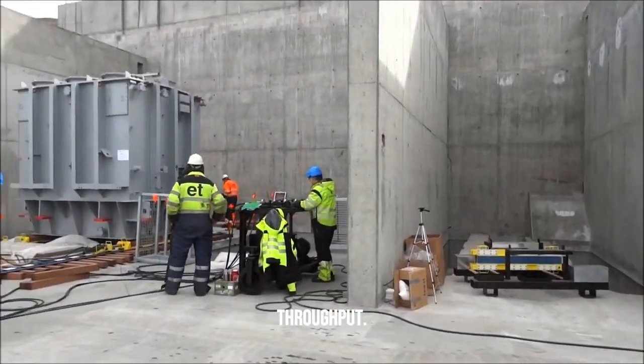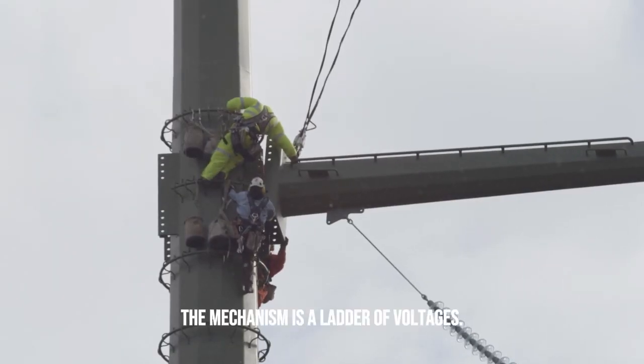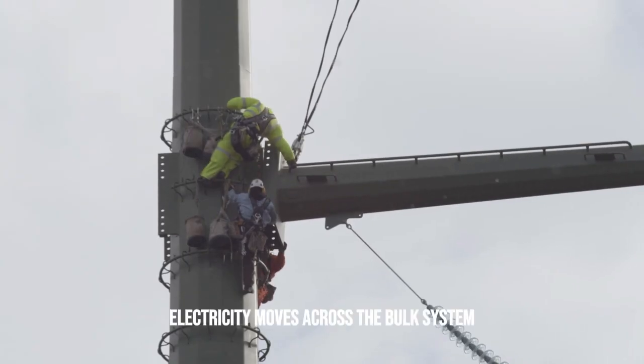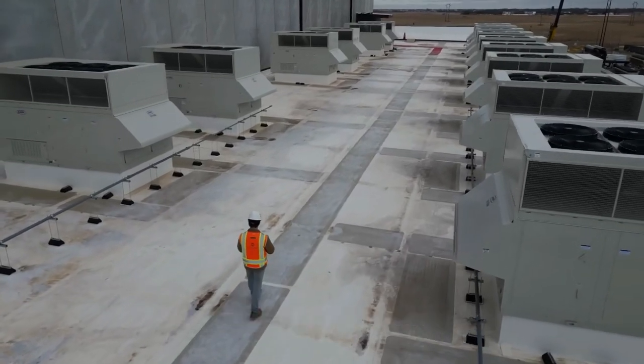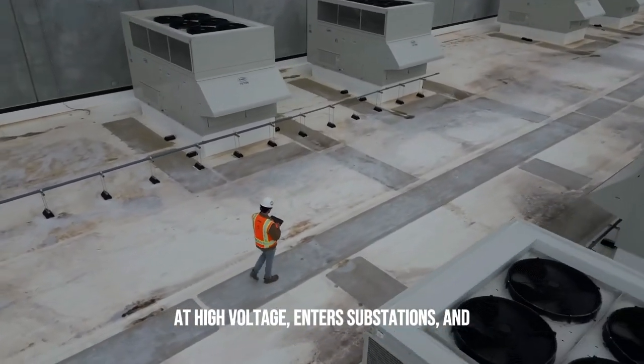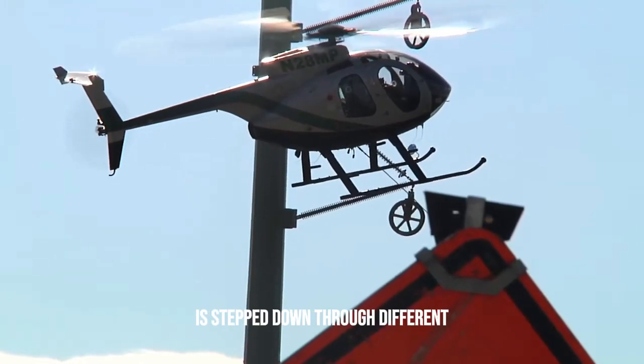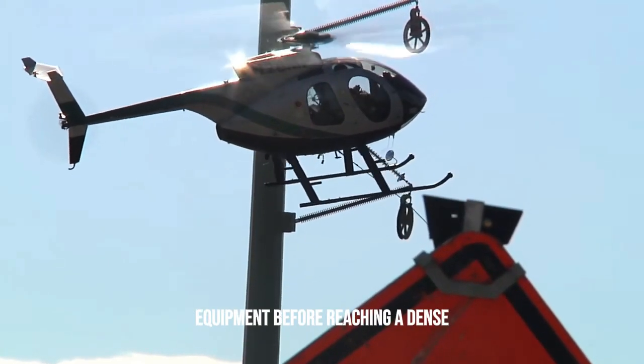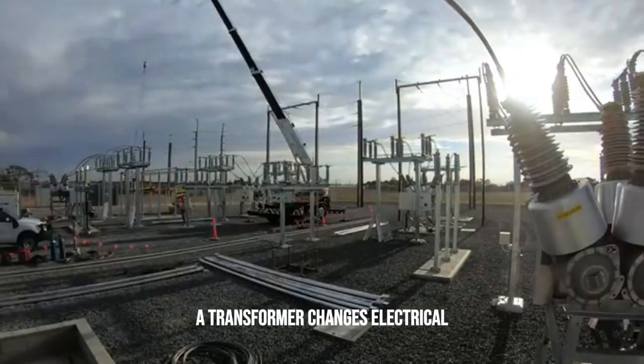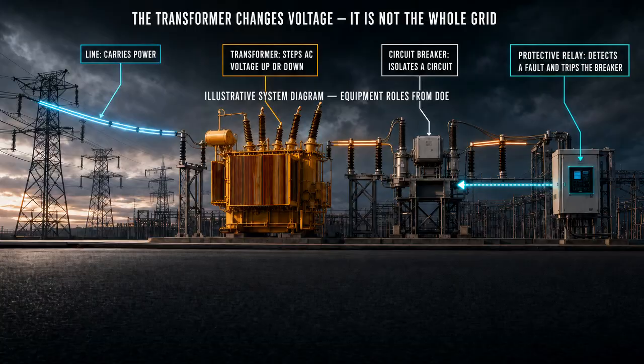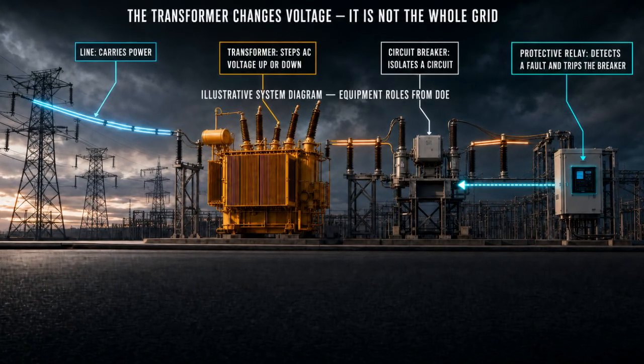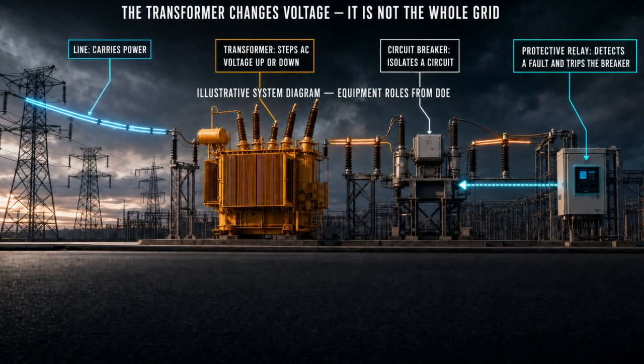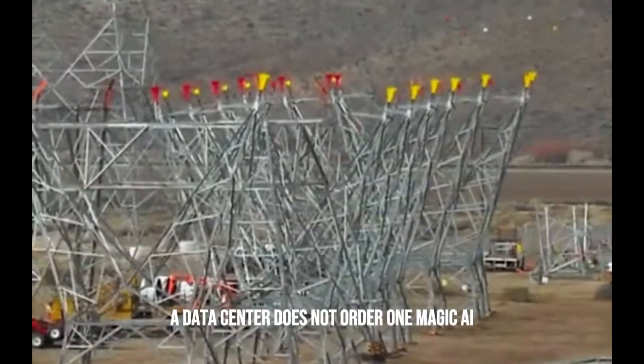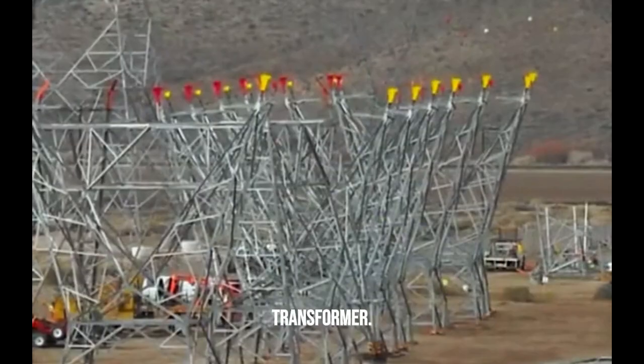The mechanism is a ladder of voltages. Electricity moves across the bulk system at high voltage, enters substations, and is stepped down through different equipment before reaching a dense computing campus. A transformer changes electrical conditions. It is not the generator, transmission line, breaker, or control system. A data center does not order one magic AI transformer.